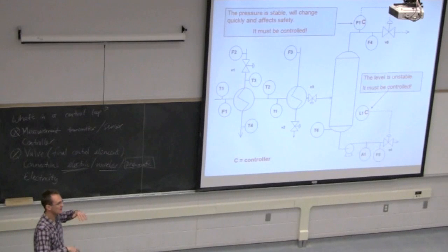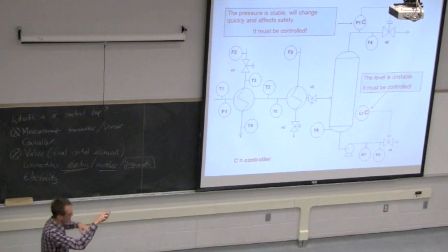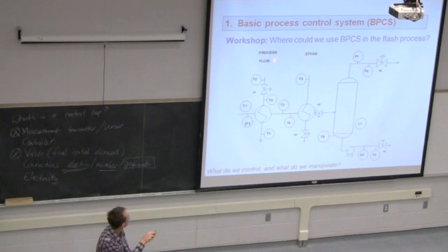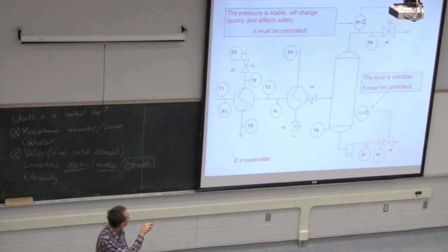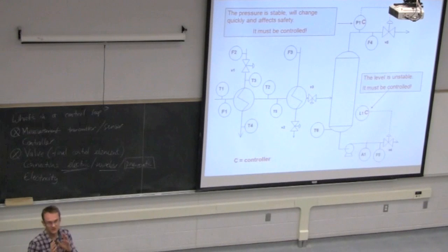So they're controlling heat to this feed stream coming in. So they're heating up the stream. You recall from the previous slide, this is a hot fluid stream, this is a hot steam. Both are coming in and exchanging heat and heating up this feed. So if they're, let's say, at 60% operation, both of them normally at 60% and there's a failure, should they go to 100% or should they go to zero?